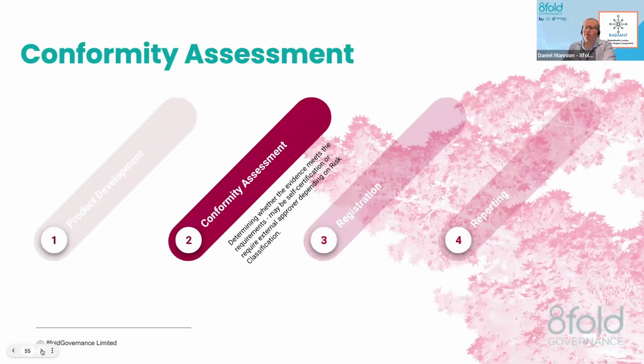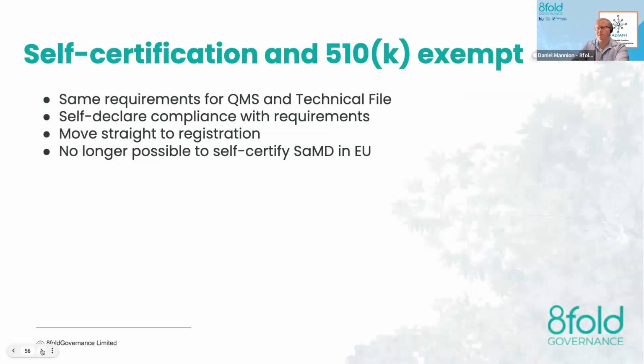There are a number of different routes for conformity assessment, which is the process for checking that you have met those regulatory requirements. So in the UK, EU, and US, there are different methods of self-certification. 510K exempt is what it's called in the US. And as I mentioned, that is you declare that your software, your medical device is safe and effective, and that's it. You're finished. That's the end of the process. If you're class 1 or 510K exempt for the US, that's the mechanism that you would use. You move straight to registering the product with the regulator.